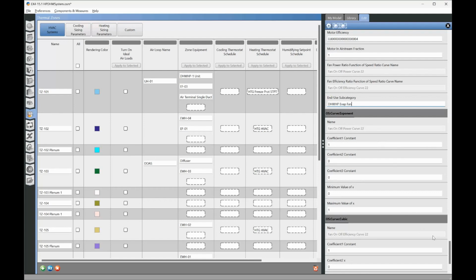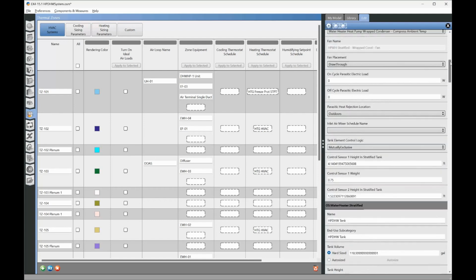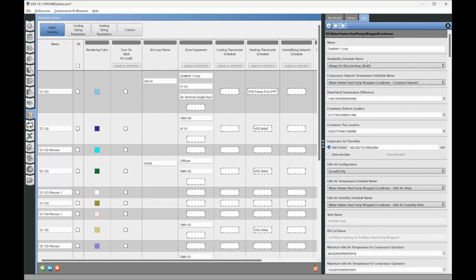And then we can go back up to the top and take a look at what we have here. So we have availability schedule. This is telling the control system when this hot water heater is available. And right now we just have it set to available all the time. But if you had some sort of scheduling where you didn't want this thing to operate, that's where you would put this schedule in.